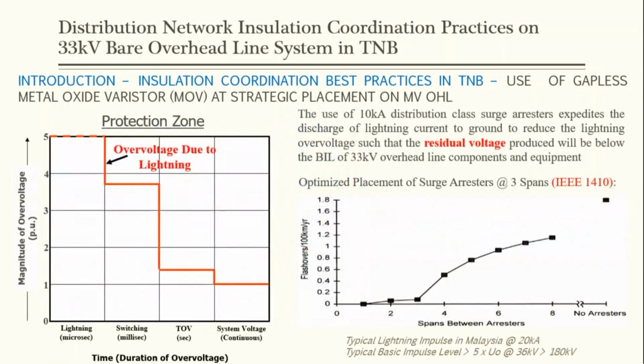The use of 10 kA distribution class surge arresters expedites the discharge of lightning current to ground to reduce the lightning overvoltage, such that the residual voltage produced will be below the BIL of 33 kV line components and equipment. If we can see this diagram here, we have the continuous system voltage, the TOV, temporary overvoltage, the switching overvoltage, and the lightning overvoltage.